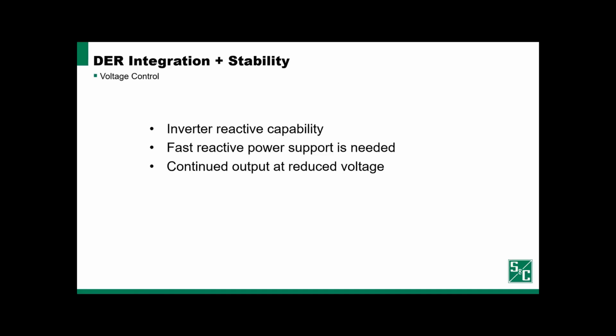With inverters displacing rotating machines, there's a need to maintain the voltage control for the bulk system that rotating machines have traditionally supplied. This requires reactive power support. Legacy inverters in particular often were designed to maintain only unity power factor at peak active power output, because this is a cost-effective design to supply power and focus on active power, which is typically compensated by markets, over reactive power, which is often not compensated by markets.